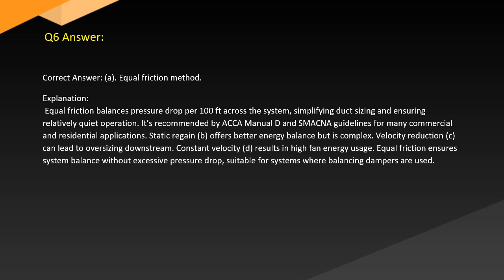Static regain B offers better energy balance but is complex. Velocity reduction C can lead to oversizing downstream. Constant velocity D results in high fan energy usage. Equal friction ensures system balance without excessive pressure drop, suitable for systems where balancing dampers are used.